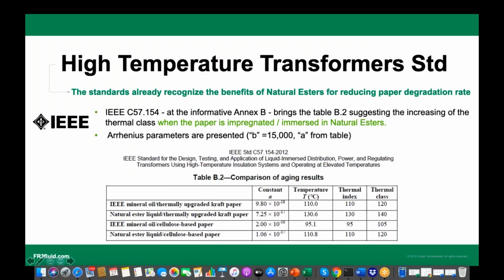So these are again extracts from IEEE, IEC, and BIS standards. The standards are available, whether it's IEEE C57.154, or IEC 60076 part 14, or BIS 2026 part 14. They all have the same standard, same table, and you can go for a transformer with a dual rating, high temperature design, with conventional losses, and the transformer will have the capability to take extra load during peak hours. That's what will be my next slide. Let's move on.